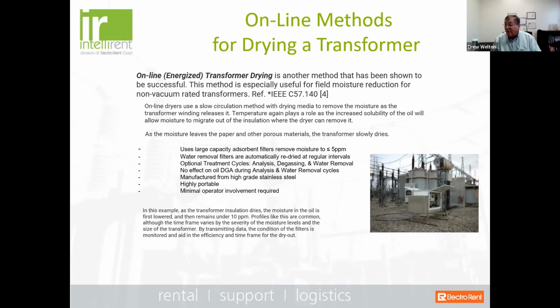So basically, these online dryers use either a low volume or a high volume pump to actually extract the oil, removing the water and removing the moisture from the oil while it's online, and it's not going to drop your oil levels down below a critical level, especially if you have a conservator tank. It really doesn't use that much, but this has been proven to be quite effective. And some of them, I know the ones that we rent, actually have a self-drying system where the filters will actually self-dry themselves. So it's kind of a hands-off process. And this, again, was a recommended method from IEEE C57.140. Very useful for field moisture reduction on non-vacuum rated transformers.